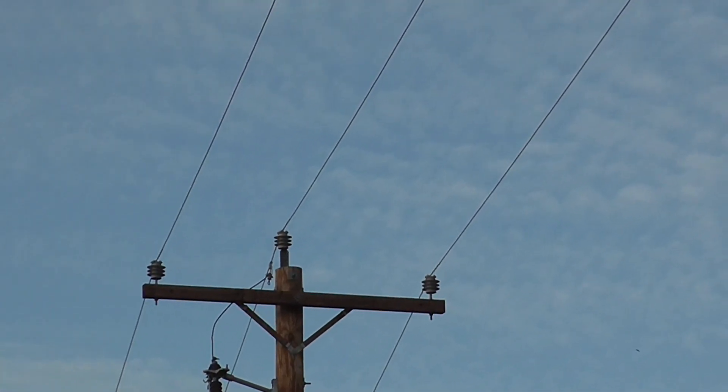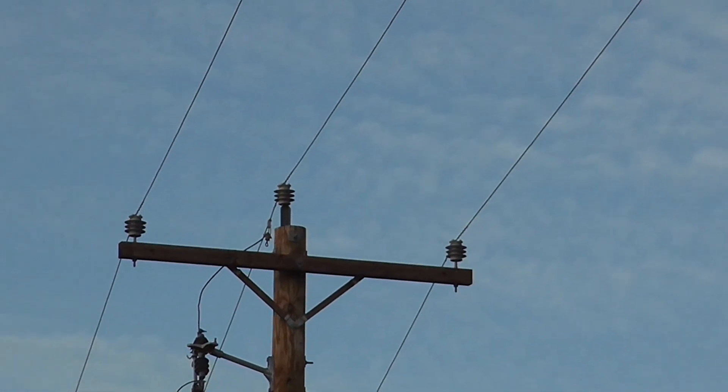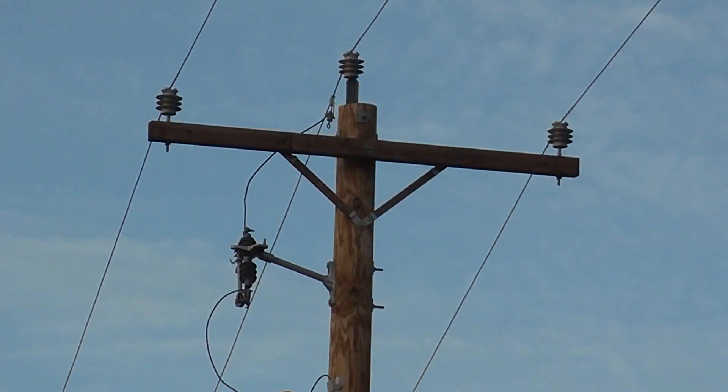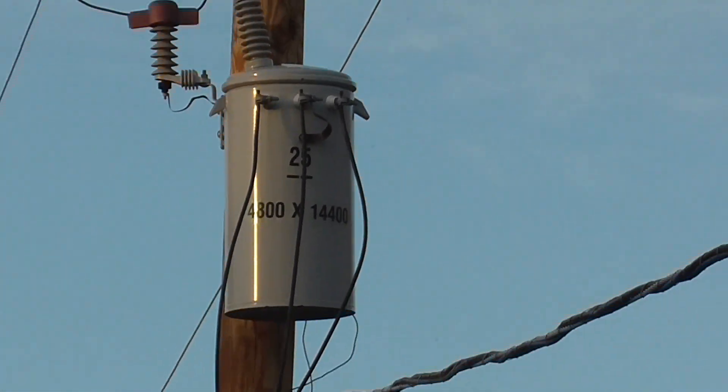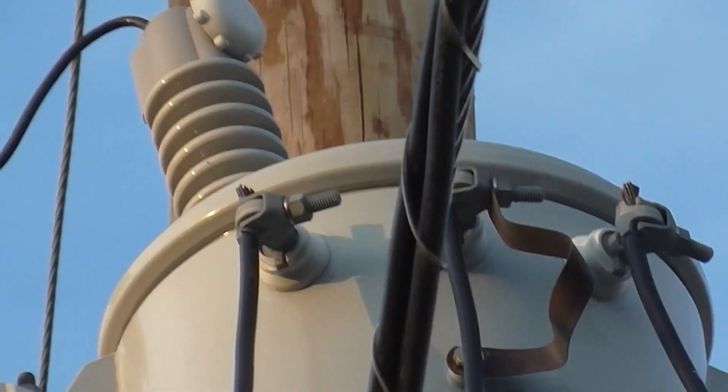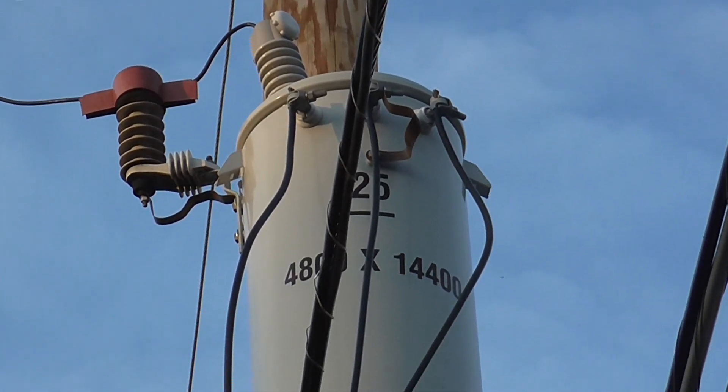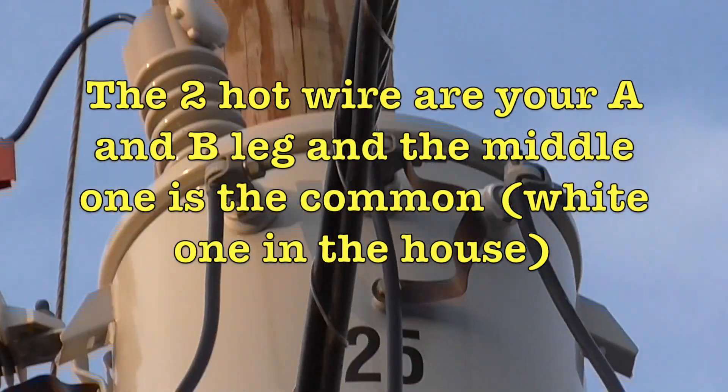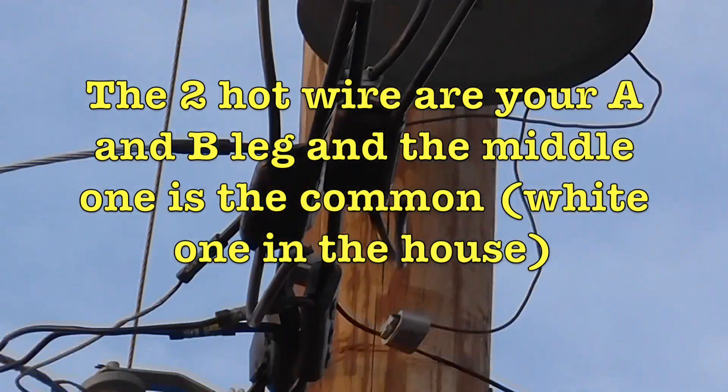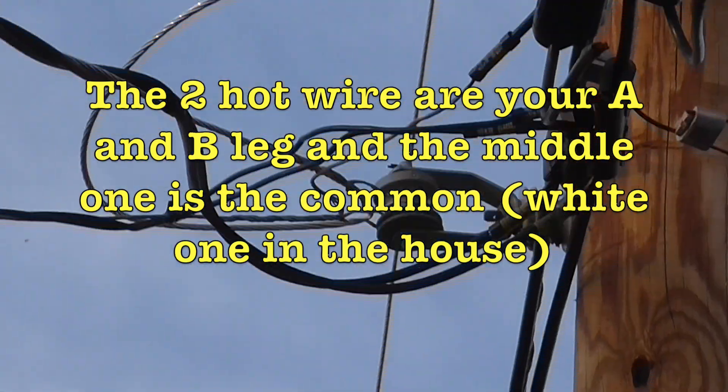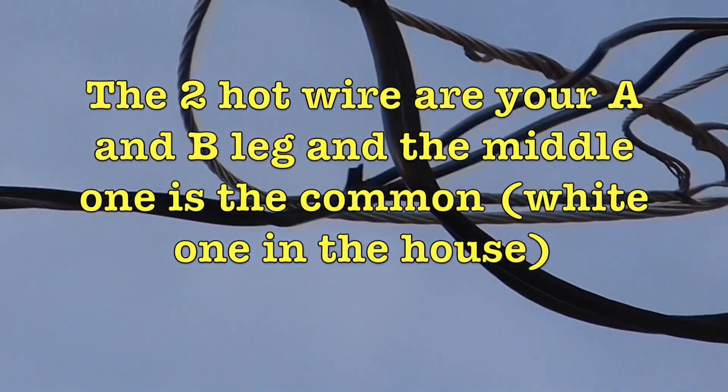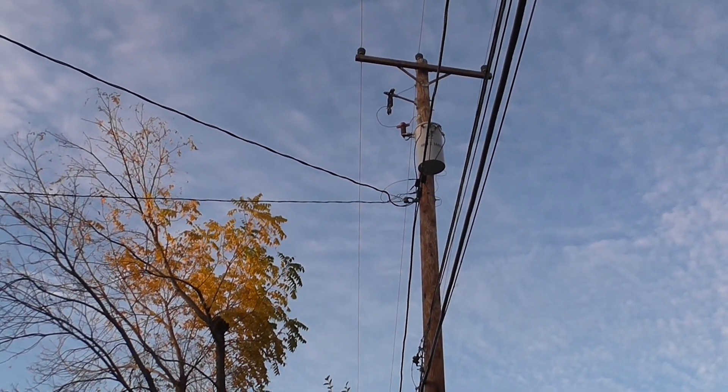So on the far top here, those three wires, that's technically three phase 27,000 volts. You see the transformer here ties into one of those three phases, then it goes down into the transformer. And on the transformer there's three wires coming out. So the three wires that are coming out, the one on the far left and then the one on the far right, those are your hots. The middle one, it's kind of like a ground.